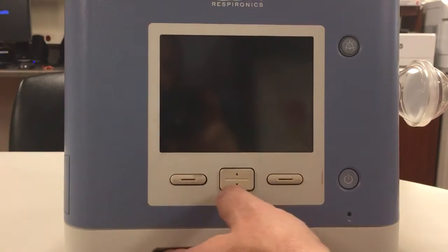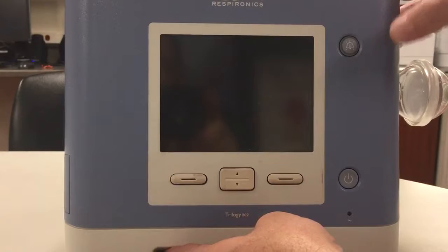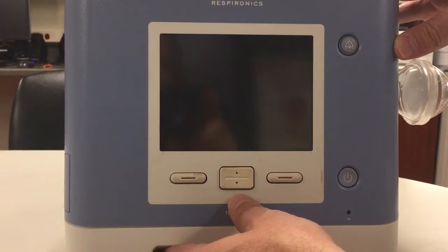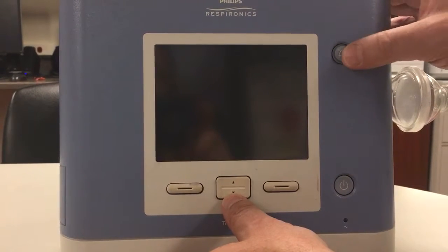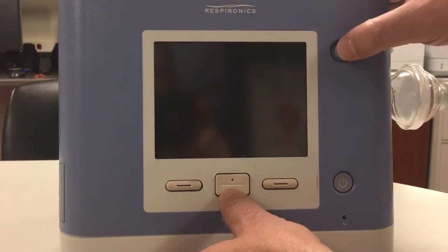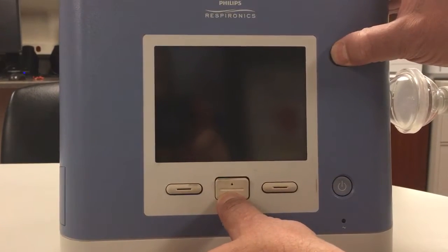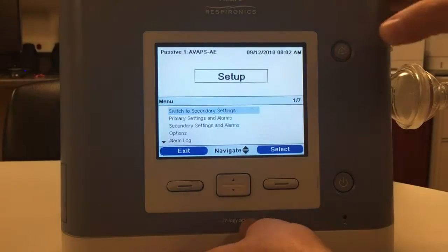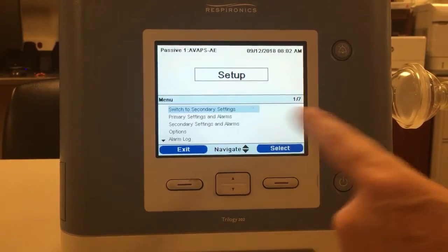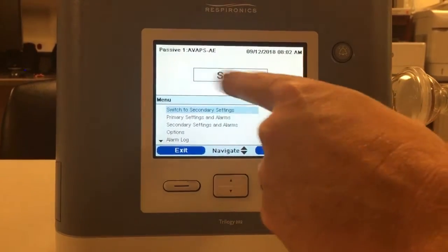Now, the secret handshake for the Trilogy is the highest and lowest button. That's how I always remember it. So it will be the arrow down button and the alarm silence button. If you press these together, keep them pressed for a few seconds, and the ventilator will beep twice. And now you can actually see you're in a setup menu.